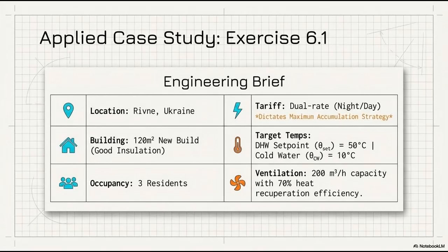And okay, how the engineers solve for this thermal leak is the most elegant, wild workaround I've ever seen. It really is. Wait, so instead of creating a separate, complicated thermodynamic formula to account for the lost energy, they just mathematically pretend the tank needs to hold more physical water. Yeah, it's brilliant in its simplicity because heat loss depends on all these complex variables. The surface area of the tank, the ambient temperature of the room, the thickness of the insulation jacket. Too many moving parts. Right. So instead of bogging down the primary equation with all of those moving parts, the engineers calculate the total energy lost through the tank walls and just convert that energy back into an equivalent volume of water.